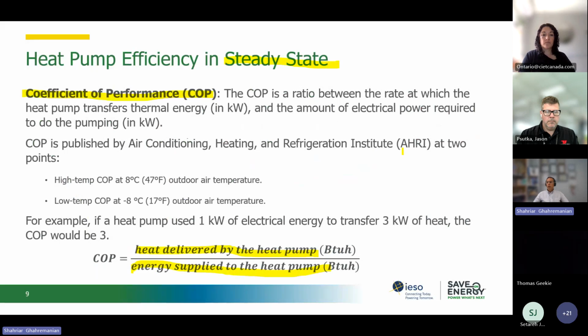The COP, based on the AHRI, the Air Conditioning, Heating, and Refrigeration Institute, is measured at 8 degrees Celsius outdoor temperature and -8 degrees Celsius. So when you see COP, you see only two steady state COPs. But in reality, the outdoor temperature varies all the time, so the COP changes. We need to remember that this COP is a steady state efficiency of the heat pump. Typically, for a heat pump, 1 kilowatt of electric energy can transfer up to 3 kilowatts, similar to the example that I showed you, which means 2.5 to 3 times more heat transfer, and that's why heat pumps are more efficient.